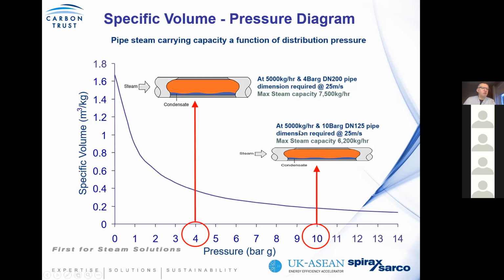Why we advocate to generate and distribute at high pressure is because installation cost for piping is quite significant when you consider not just pipes but ancillaries. So it's important that you generate and distribute at the highest pressure possible, such that you can get the lowest installation costs, but done in such a way that you can ensure ample supply of steam without creating steam starvation. And you can overcome issues such as the normal problems with systems, where a process can't achieve temperature or struggles when another process comes online. So it's important to understand that the ability to transport steam is determined by its pressure at a certain pipe dimension.